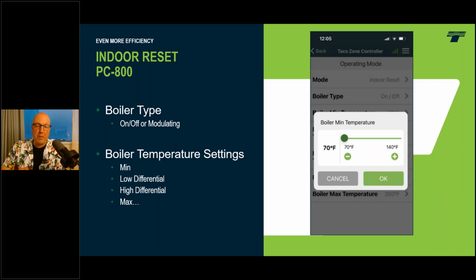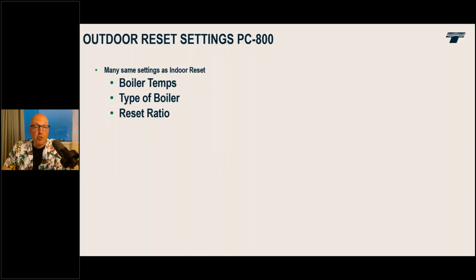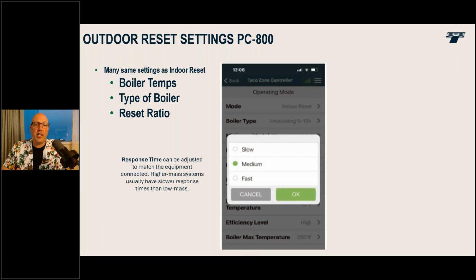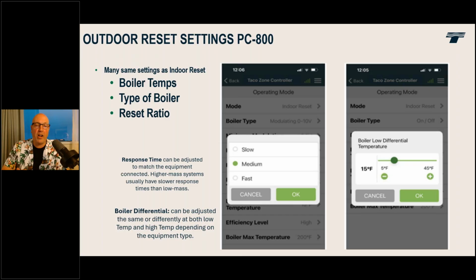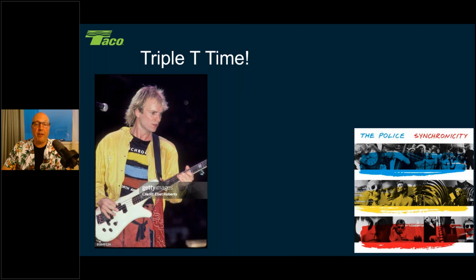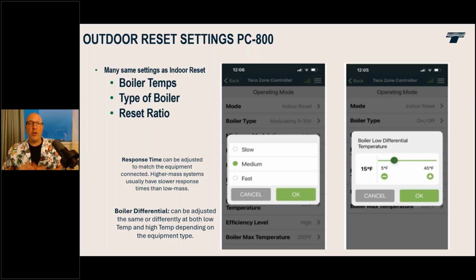All right, so that's your PC800, some of the settings that you see there for indoor reset. Here's your outdoor reset. Now, the one thing that you need to know with the outdoor reset is setting up your reset curve. All right, so you'll have, again, that differentials. What we mean by response time, meaning is it high mass versus low mass? All right, how fast is that boiler going to heat up and cool down out there? So those are the bunch of things that we have.